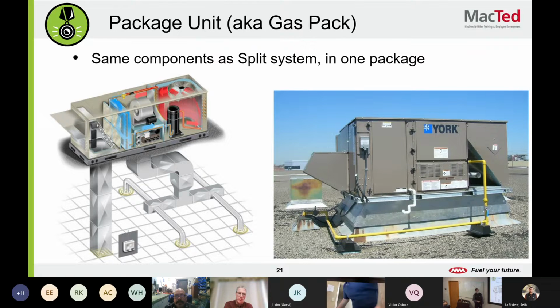You see anything wrong on this picture? Is that hood upside down? No, what we're trying to point out is, I don't know if you see this lovely P-trap here. Yeah, what is going on there? I don't know what they were doing with that one. Seth, you had a theory, right? Yeah, it's a little shallow for a condensate trap. It looks like maybe it wasn't glued and it swung down. Yeah, that's what I'm thinking. It just flopped down. Yeah, that makes so much more sense.